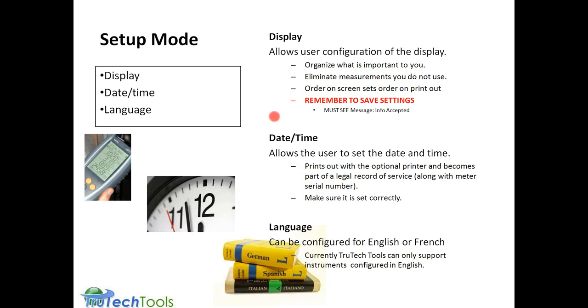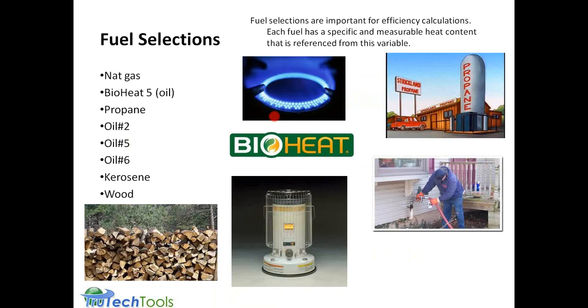And then we covered the language issue. The next screen is fuel selection, and that's where you can pick which fuel. These are the current fuels that are available inside the combustion analyzer. Natural gas, and these are the order that they go in, the sort order as you move down the screen. Natural gas, bioheat 5, which is a combination of 95% fuel oil number 2 and 5% biodiesel. It's currently an approved fuel by, I believe, all the oil heat manufacturers. Propane is the next fuel, oil number 2, oil number 5, oil number 6, and then getting into kerosene and wood. Those are the different types of fuel.